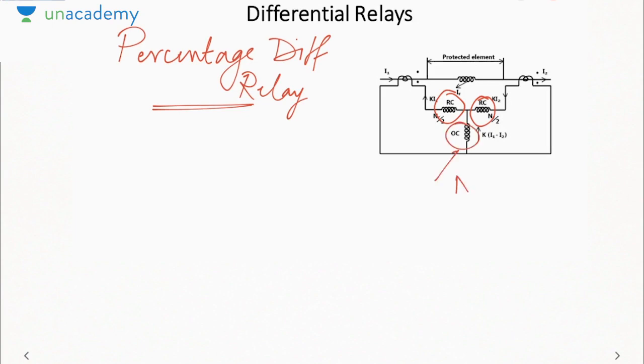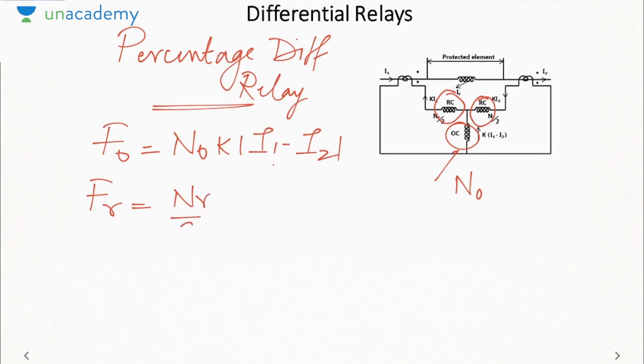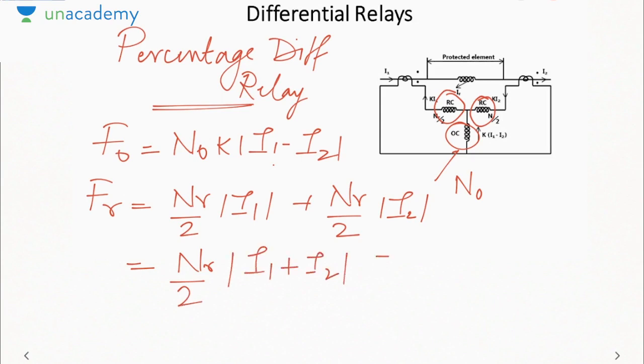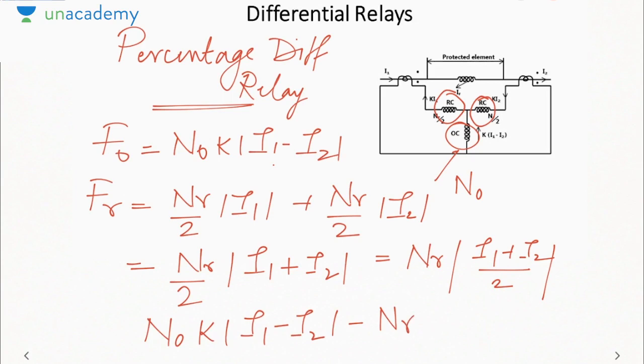Now, suppose the operating coil has N0 number of turns, then the MMF of the operating coil will be N0 K mod I1 minus I2. The MMF of the restraining coil will be NR by 2 mod I1 plus NR by 2 mod I2. Or we can say, since both currents are taken as positive, NR by 2 mod I1 plus I2. Or we can say NR into mod I1 plus I2 by 2. Now, when the difference in the MMF, or the magnetic field produced by these two currents, is greater than the pickup value, then the relay will operate. That means N0 K mod I1 minus I2 minus NR, sorry, here there will be a K, mod I1 plus I2 by 2, is greater than I pickup. If it is greater than I pickup, then the relay will operate.